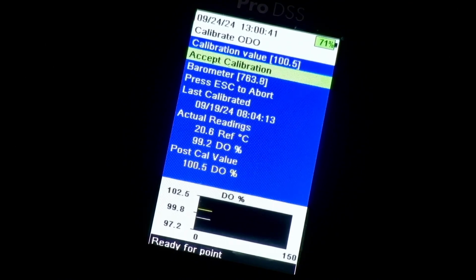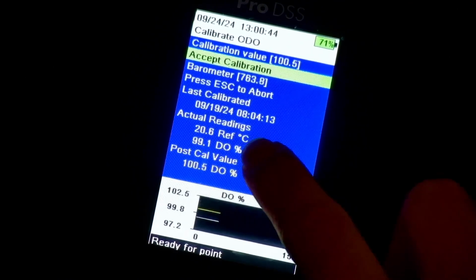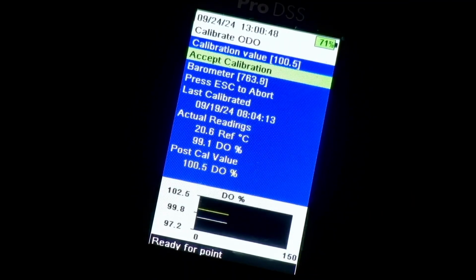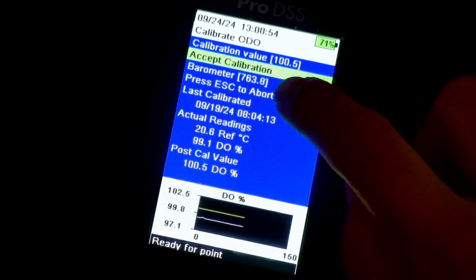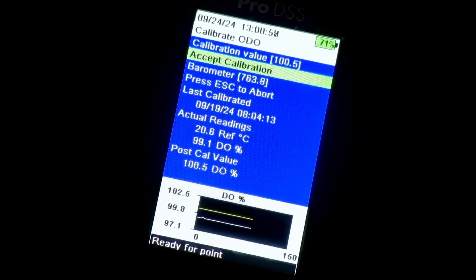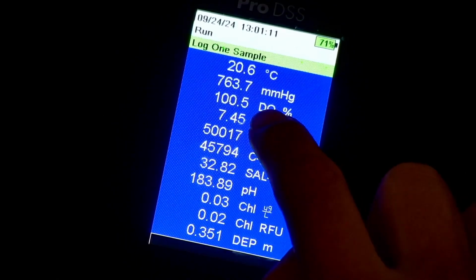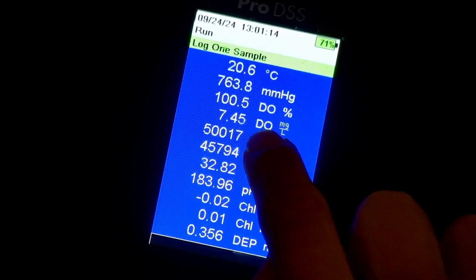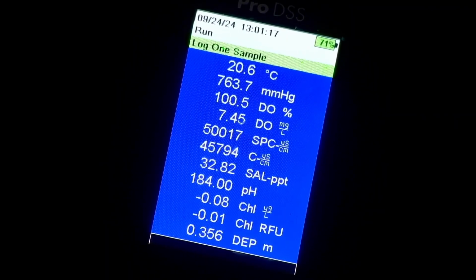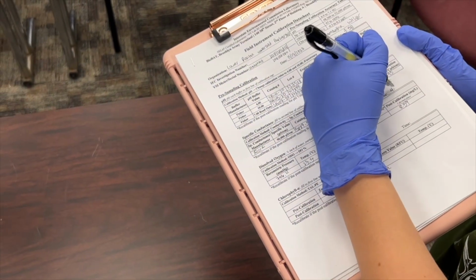Use the numbers under actual readings to fill out pre-calibration percent saturation on the calibration sheet. SAT is short for saturation. You will also need to record the barometric pressure and temperature. Select Accept Calibration, and once it's complete, it will return to the calibration menu and display the message, Calibration Successful. Escape to the home screen and fill out the values for post-calibration DO percentage and post-calibration mg/L on the calibration sheet. The post-calibration value for percent saturation should be between 97 and 103%. Record the time and if recalibration was performed.